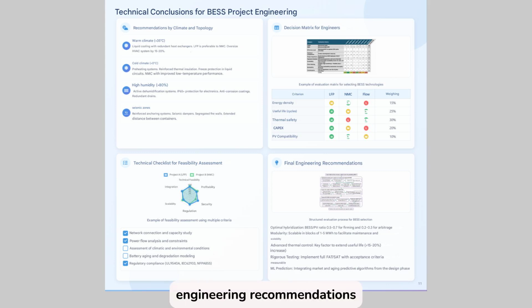Some final engineering recommendations include optimal hybridization, with a BESS PV ratio between 0.5 and 0.7 for firm capacity, and 0.2 to 0.3 for energy arbitrage. Modularity: it is preferable to scale in blocks of 1 to 5 megawatt-hours to facilitate maintenance and availability. Advanced thermal control: improve service life by more than 15% and less than 20%. FAT/SAT testing: mandatory with objective metrics. ML prediction: integrate AI models from the design phase to adjust aging and dynamic behavior. These recommendations are the result of integrating operations, regulations, profitability, and safety into a single technical vision.